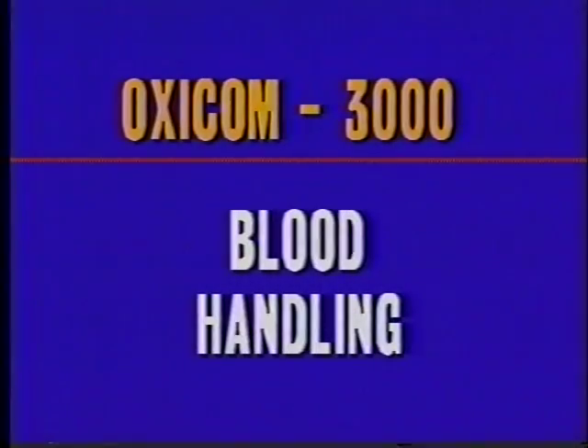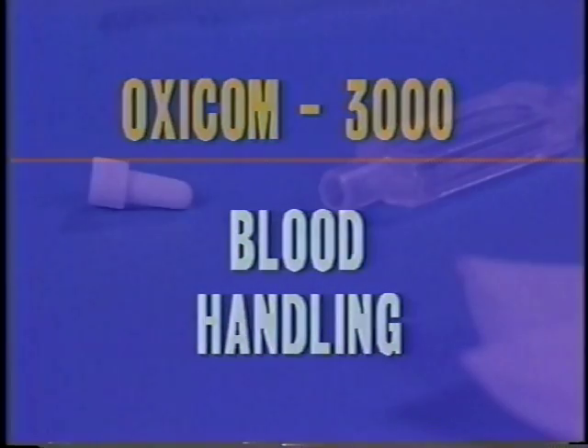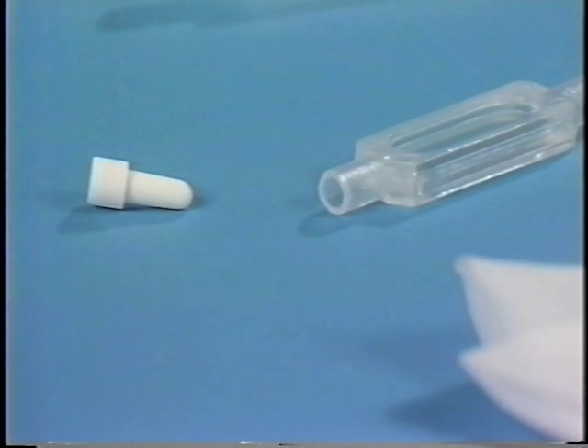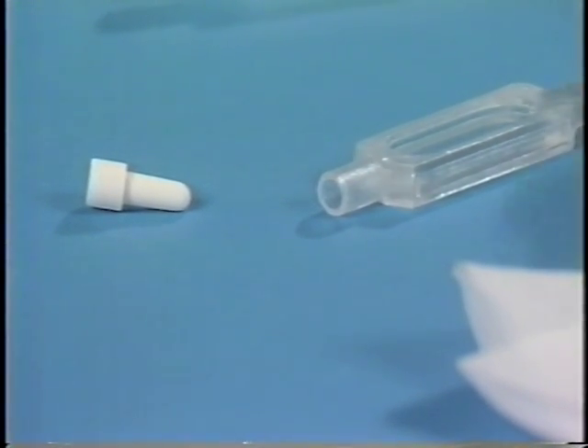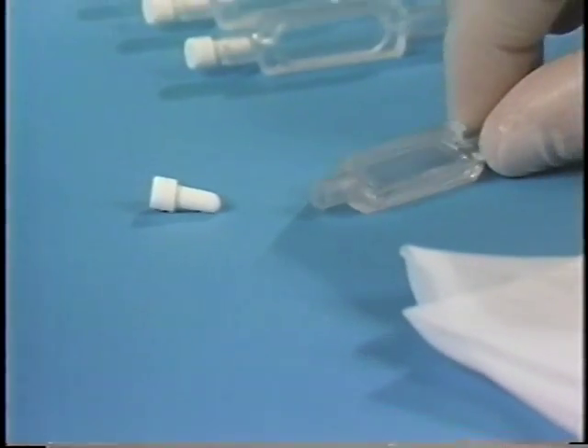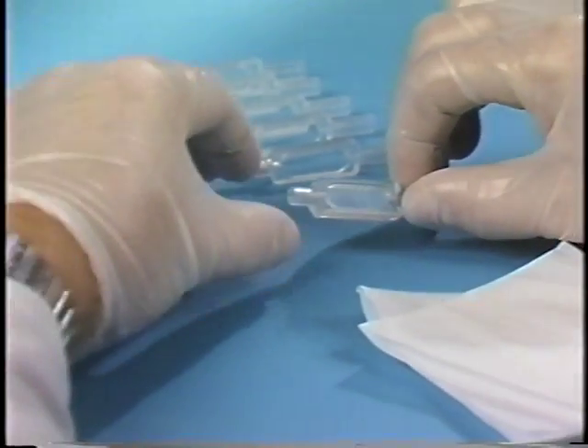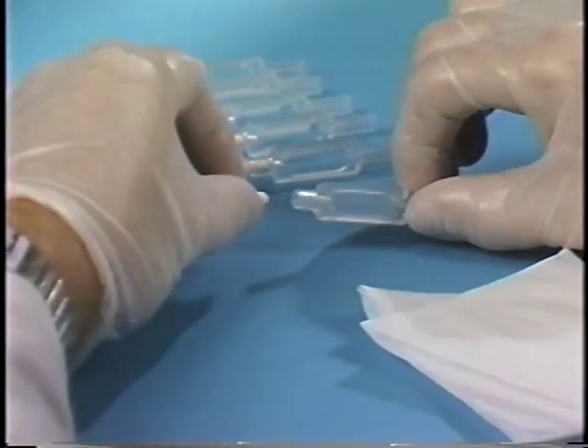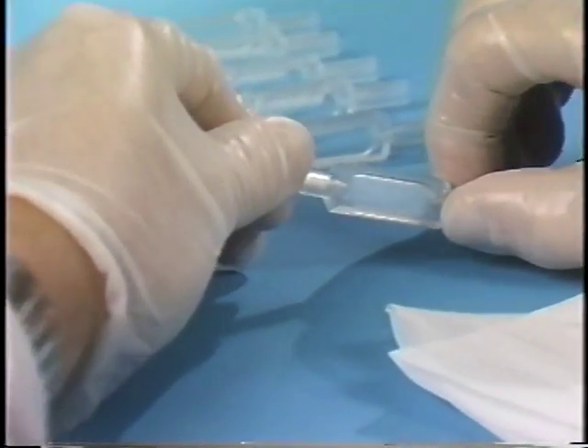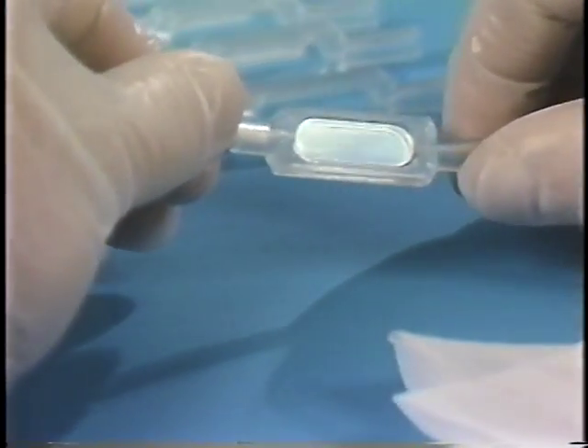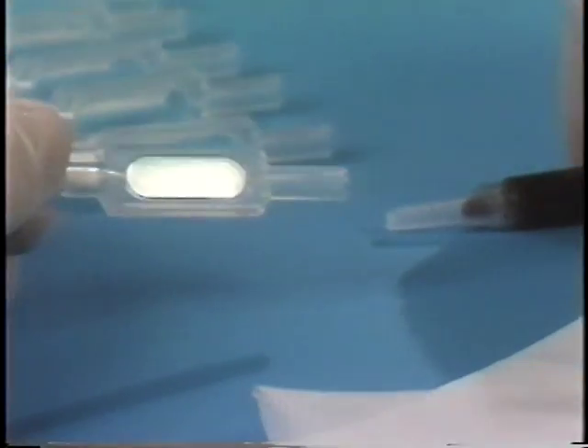Blood handling. For proper calibration and personal safety, please follow these techniques consistently. Before any samples are drawn, prepare all cuvettes needed during the cath procedure. Please use special care while handling the cuvettes. Avoid touching the windows or large flat sides. Place the porous filter plug firmly into the short neck of the cuvette. The long neck is placed on the syringe.